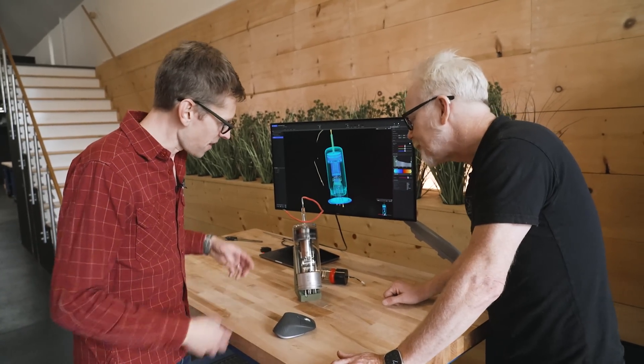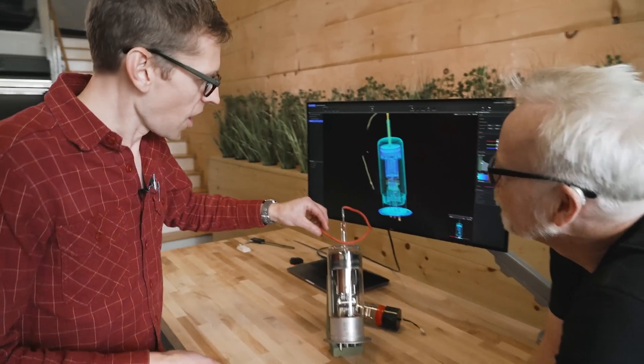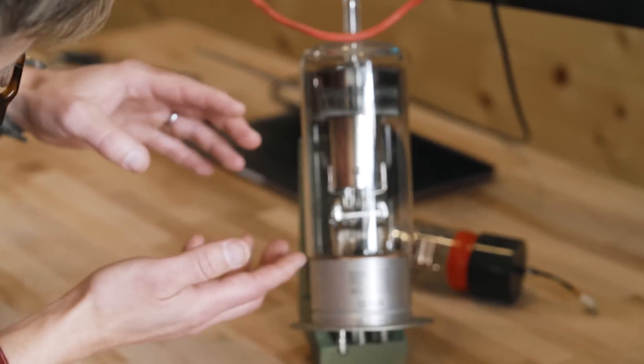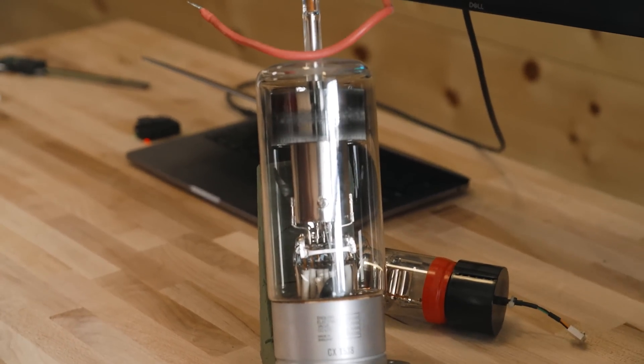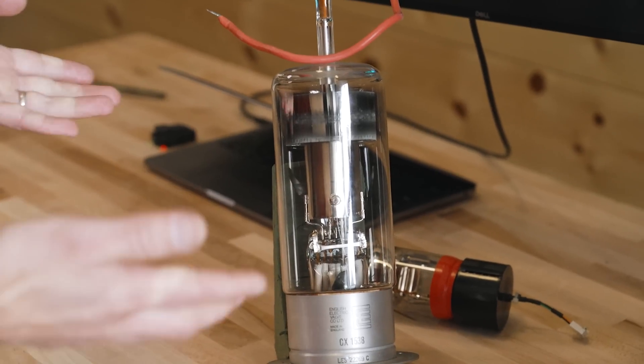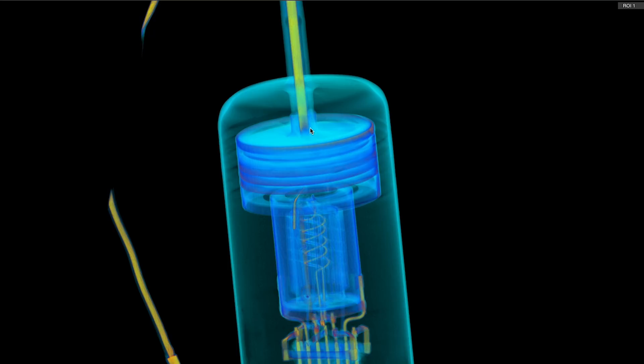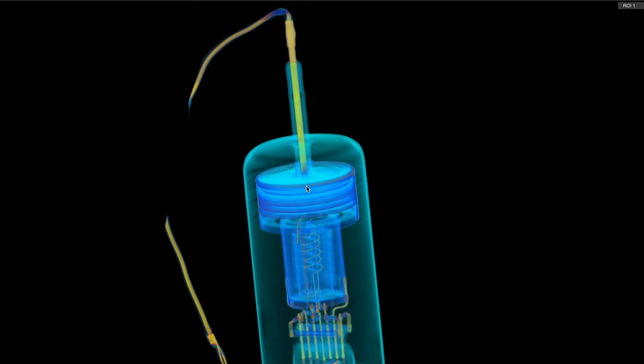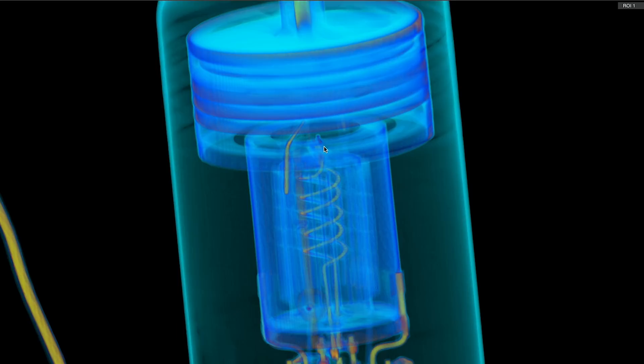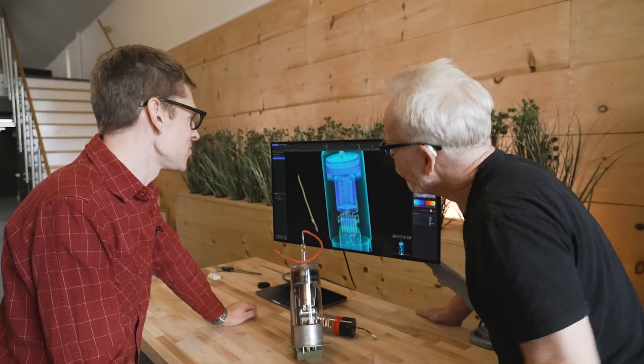Yeah, so that little tube heats up, generates enough hydrogen. Now what does the hydrogen do for the electrical current? Yeah, so the hydrogen gas is there to help create a plasma when this thing gets going. So you have an anode at the top here with this silicone lead - it comes through a seal in here and comes to a plate. There's a bunch of little baffles and things like that in here, but basically there's an anode, a control grid, and a cathode. But the cathode is kind of hidden inside of the shield. When we first saw this thing I was like 'what are you really going to see in the scan?' But clearly this thing is completely clear - you should be able to see everything. But it turns out these structures are necessary to make this thing work and you can't see through them. So here we are on the CT scan, and now you can see what's really going on inside this tube. So here you can see the glass seal, the feed-through for this anode, and where it connects to this plate. There's a bunch of discs here which are really to shield that grid electrode, and that grid is what the control element for this device. That's stopping that plasma from starting until you really want it to go, until you've said yes. Yes, exactly.